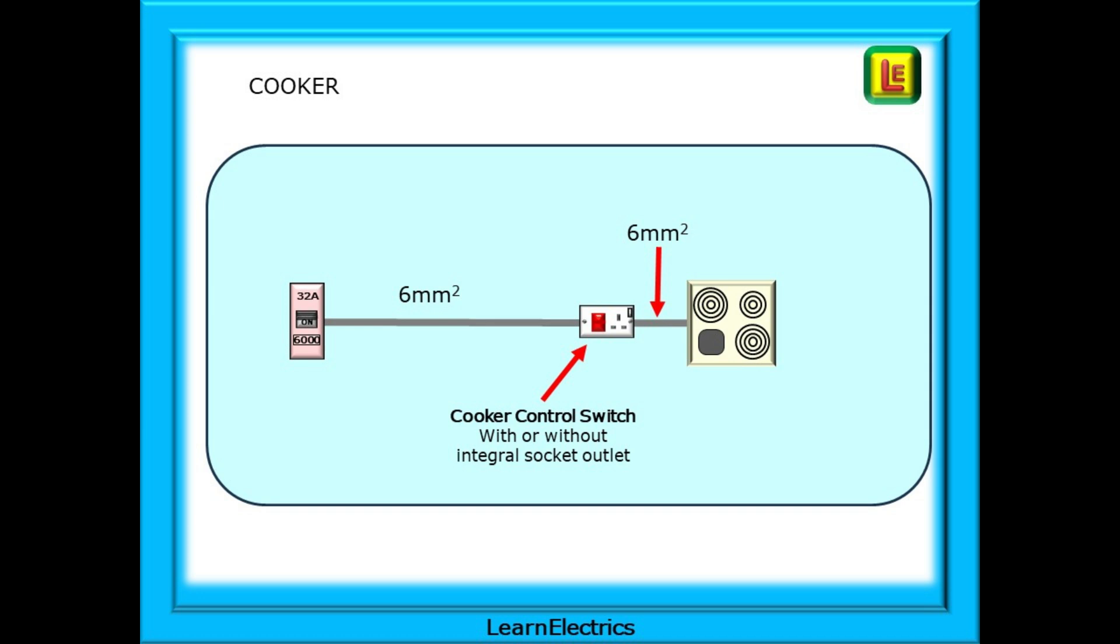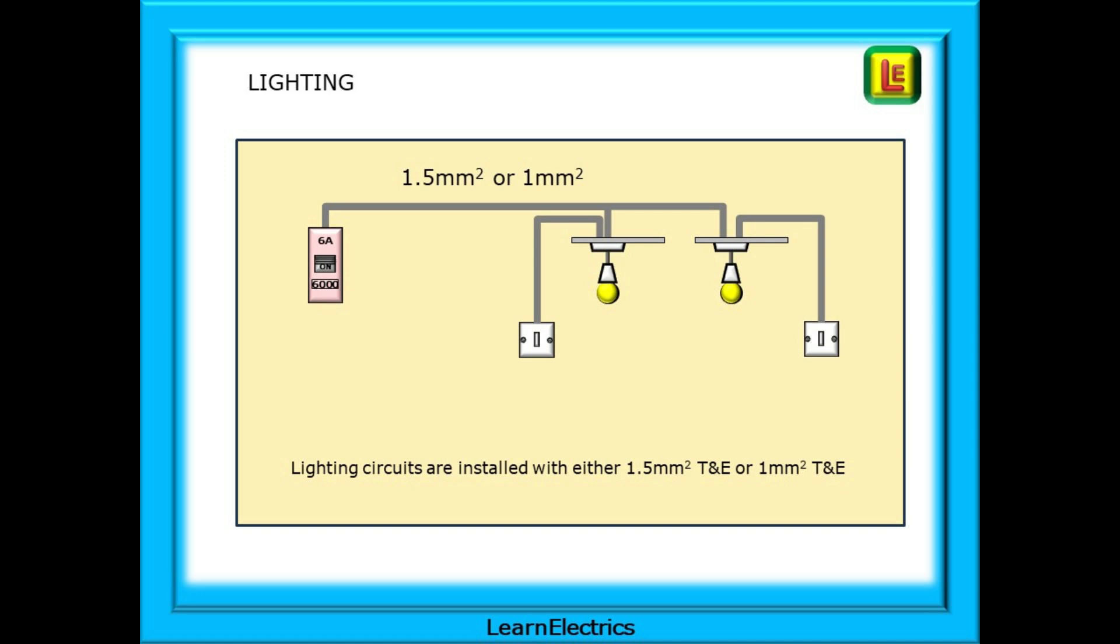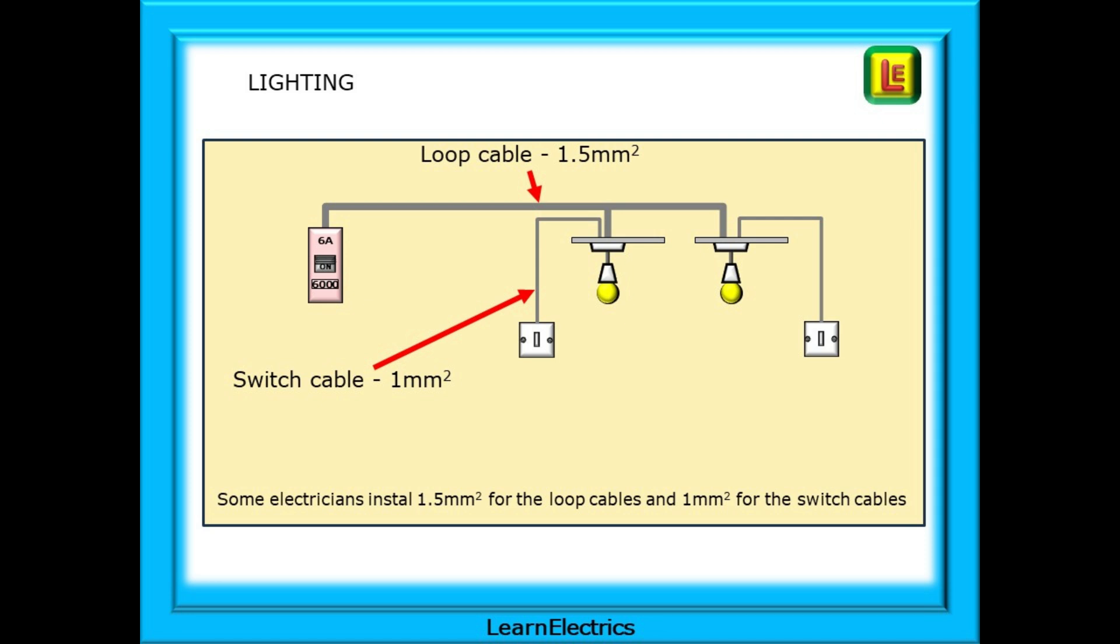Lighting circuits may only have 2 or 3 amps of design current, especially with modern low-energy lamps, and will be protected by a 6-amp breaker or 5-amp fuse using 1.5mm or 1mm twin-in-earth cable. Some electricians will use a mixture of 1.5mm and 1mm cable. They will use 1.5mm² for the loop cables, from the consumer unit to the ceiling roses and to the next ceiling rose, and then they will install 1mm² cable for the switch drops. This helps with quickly identifying which cables are the loop and which are the switch.